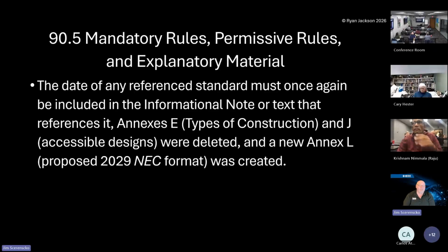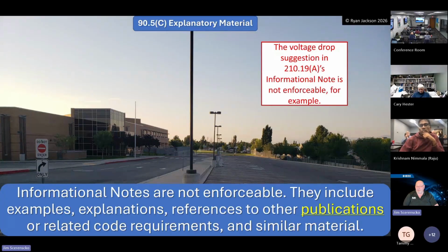So in 90.5, the mandatory rules, permissive rules, and explanatory material. Basically, the date of any reference standard must once again be included in the informational note or text that references it. Annexes E, types of construction, and J, accessible designs, were deleted, and a new Annex L proposed 2029 NEC format was created. So I think they took the ADA stuff out of the annexes in the 2026. I haven't got back that far to actually look, but I believe that's what I was told. So maybe they're going to bring them back in. Informational notes are not enforceable, okay? So if it's an informational note, it is exactly what it says. It's for information purposes only.